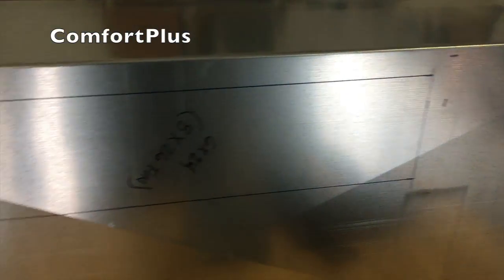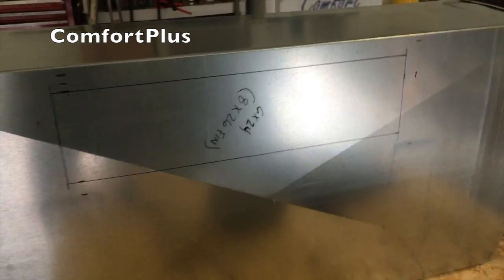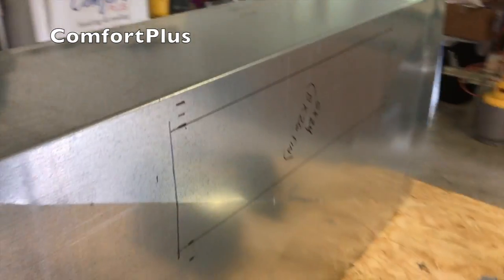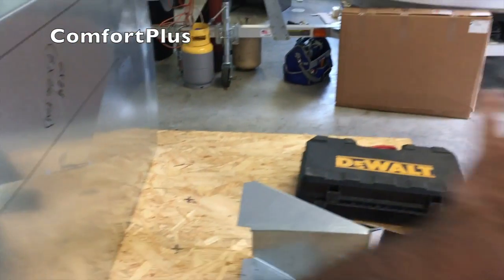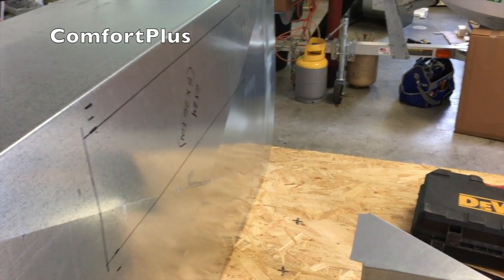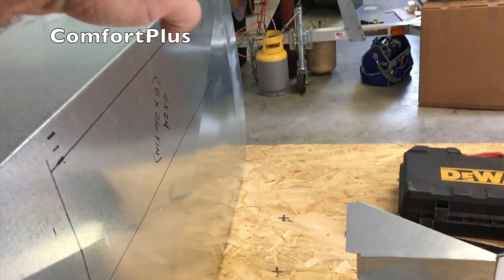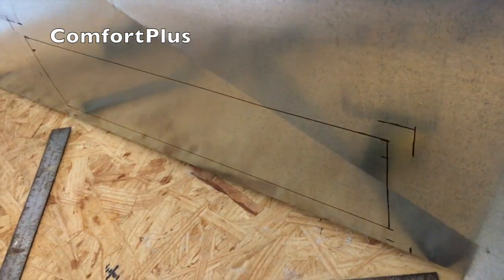Actually, the majority of the air is going to be probably coming through this duct most of the time. That's the side of the house that I actually use. So the other side, the zone will stay off most of the time, or not off, but at least at a higher temperature. So once this thing's set in here like this, you'll have this duct coming out going to what I would call my main living area, which will be right beneath the floor joist. On this side, I'll be coming out the same setup down low, because I need to miss this steel beam that we'll see when we go up under the house. So that will be the other branch duct that comes off.